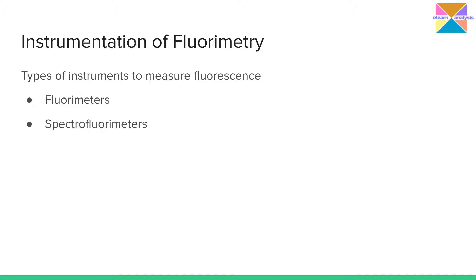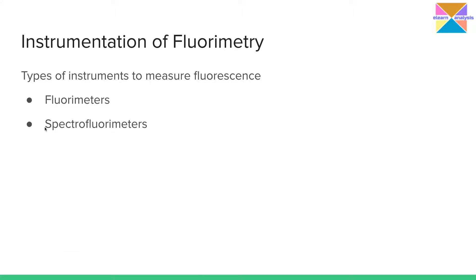We have two different types of instruments to measure fluorescence. One is the fluorometer and the other one is the spectrofluorimeter. The fluorometer is somewhat similar to the one used in UV-visible spectroscopy — that is, the colorimeter or absorption meters — where the wavelength selectors are filters. The spectrofluorimeter uses monochromators as wavelength selectors: one excitation monochromator and one emission monochromator. The fluorometer, similarly, uses primary filters and secondary filters.